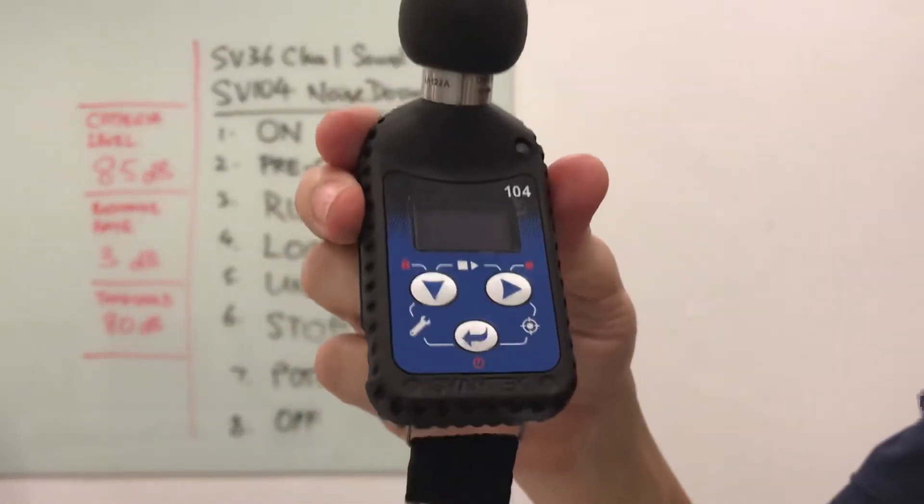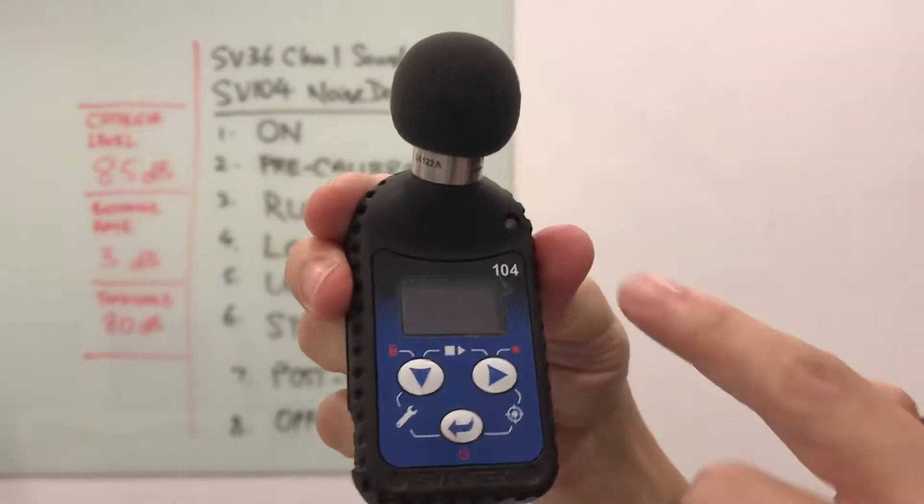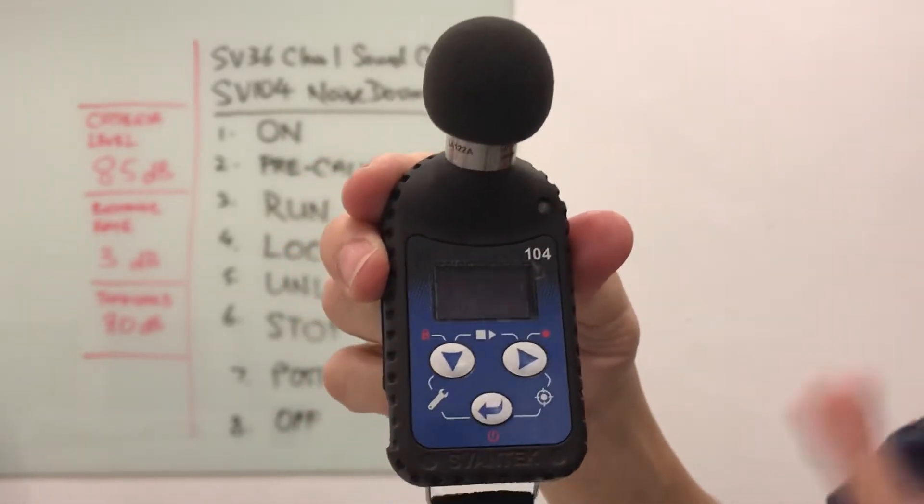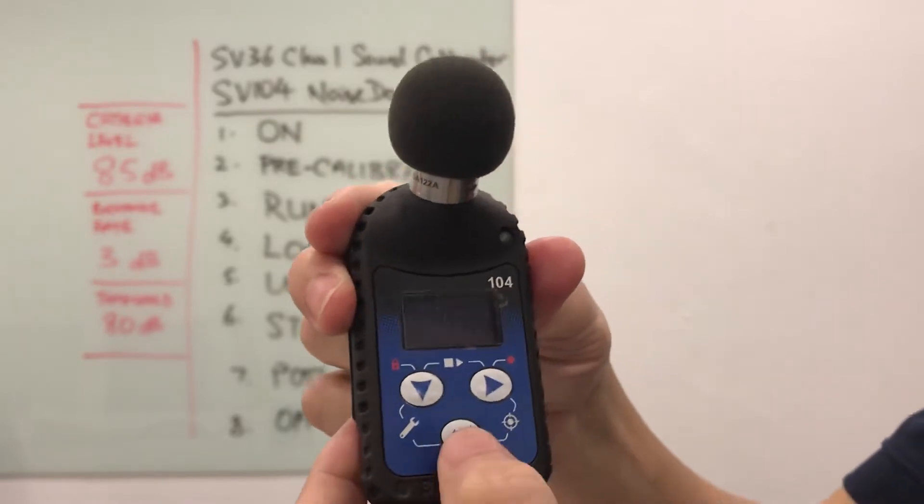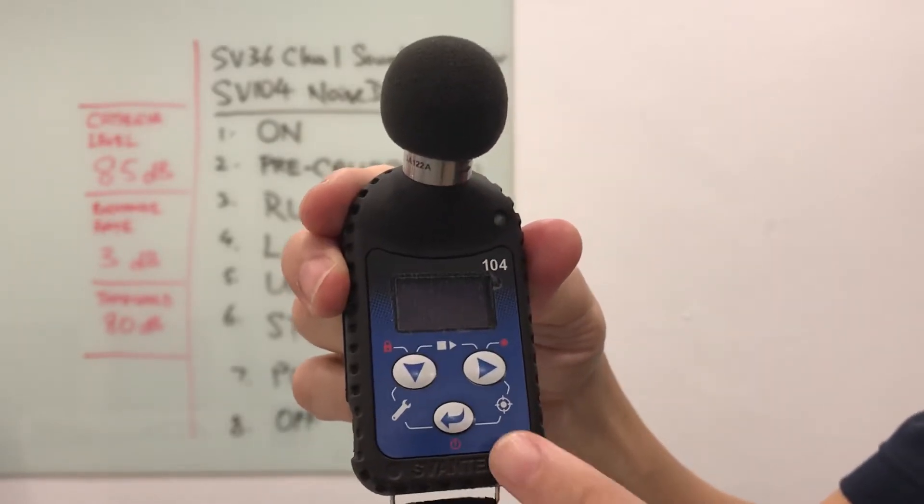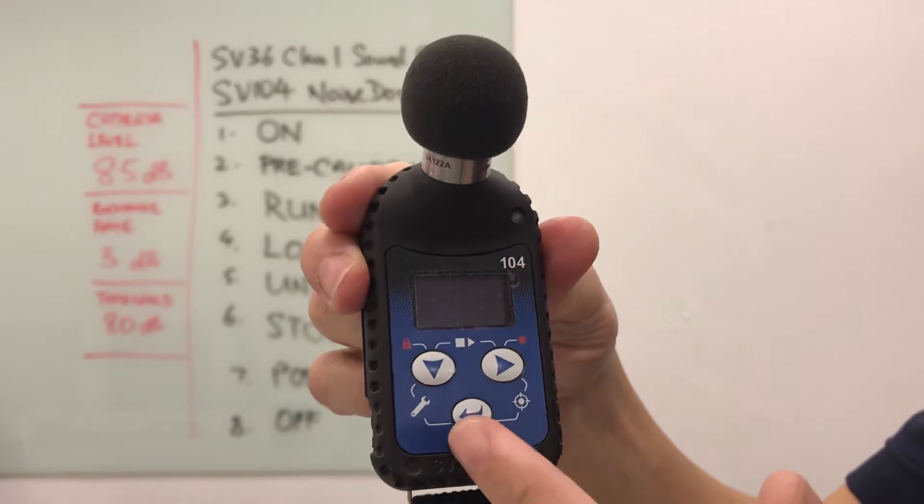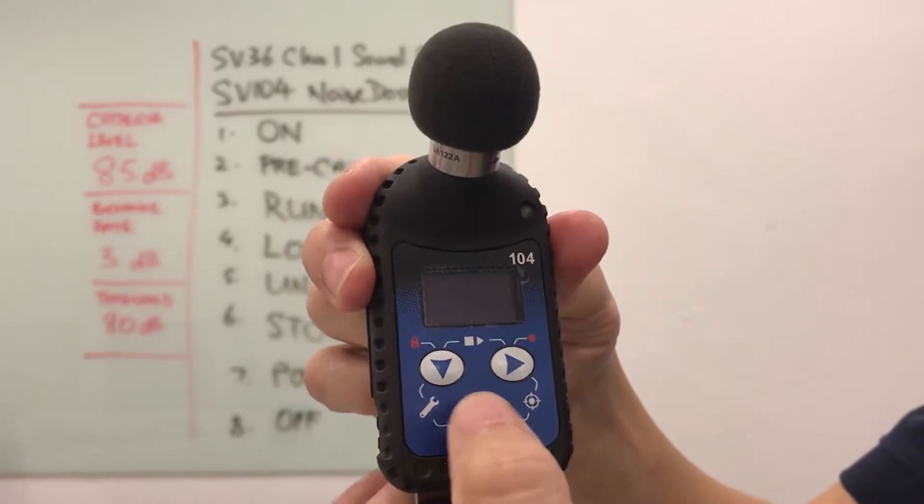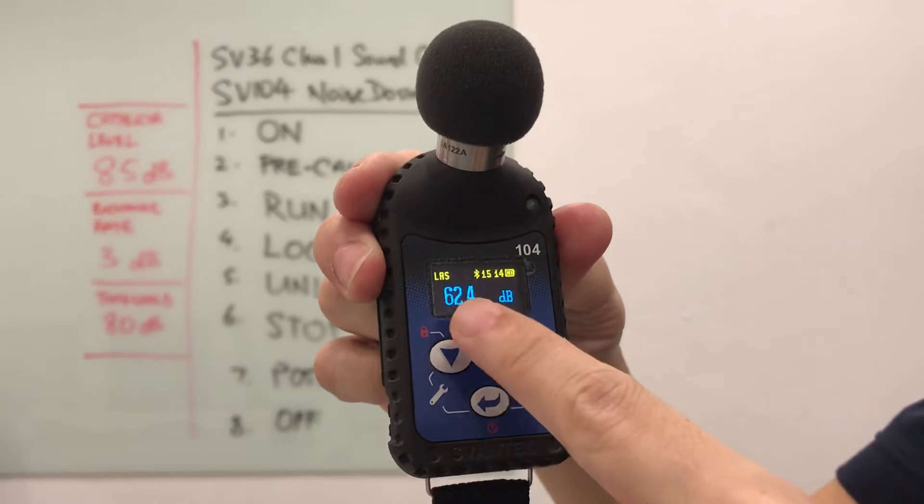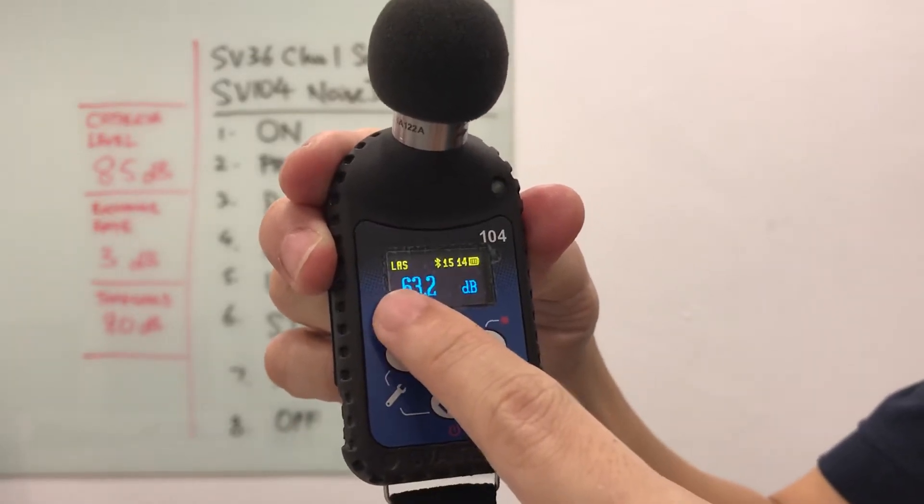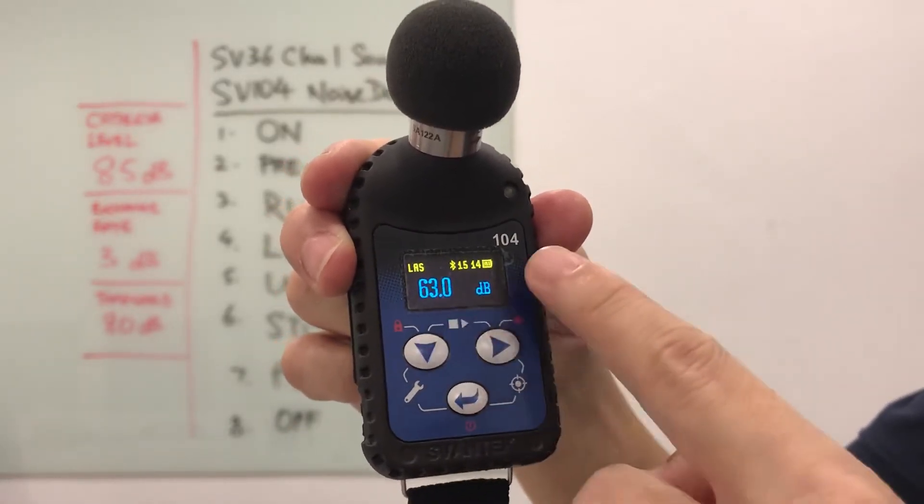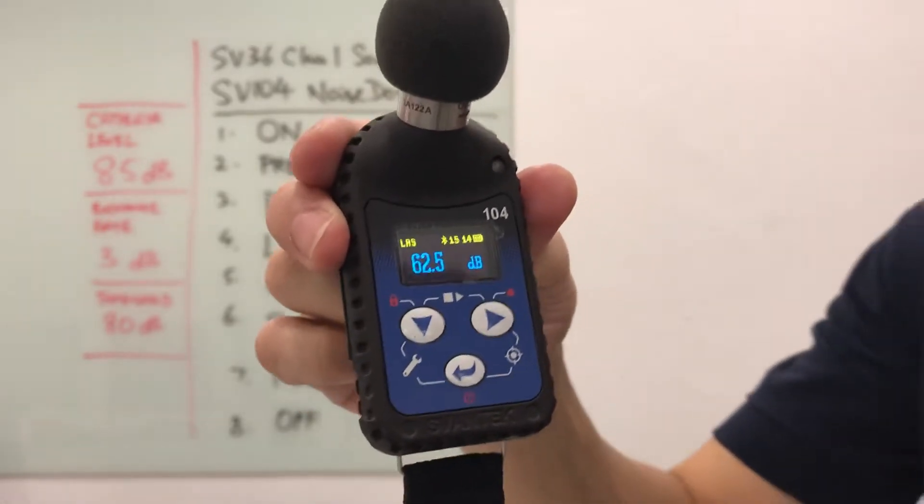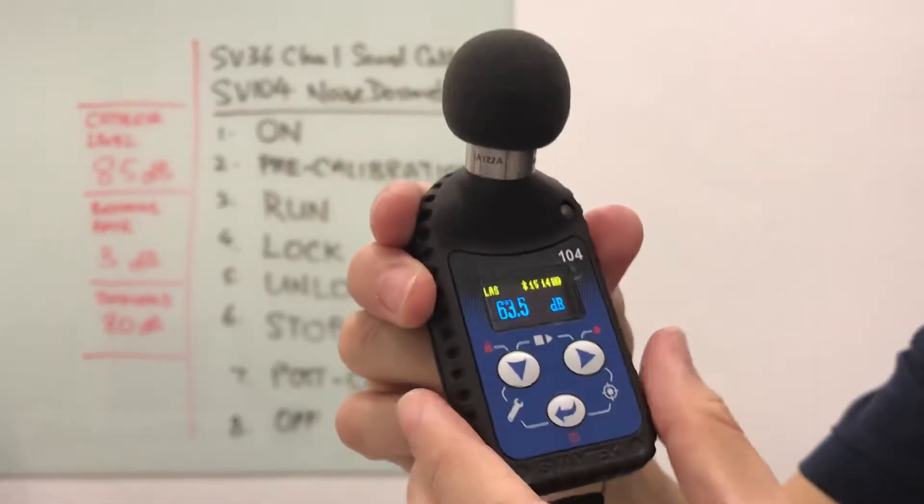Notice how the screen turns itself off. This is to save power and the LED light is not flashing because we have not started any monitoring. If I want to reactivate the display, I will just press onto the button and then I have the display showing LAS 63-64 dB and the time right now is 3:14. It is not recording, it is not running yet.